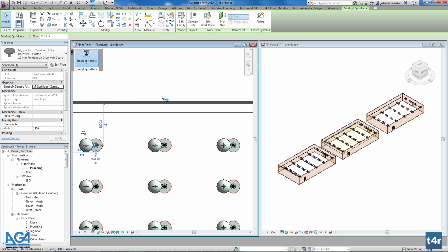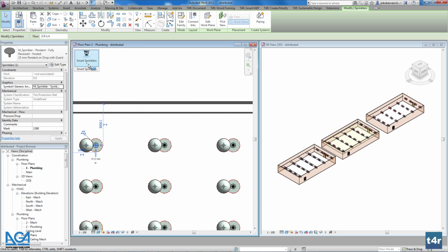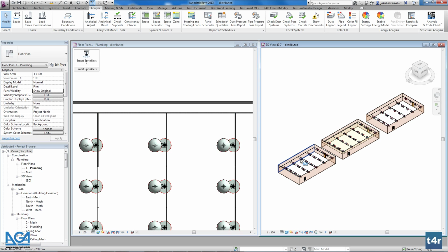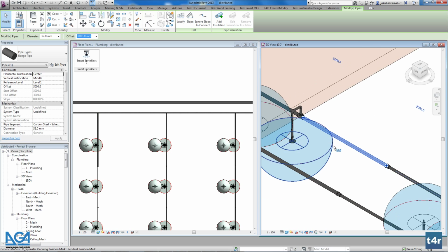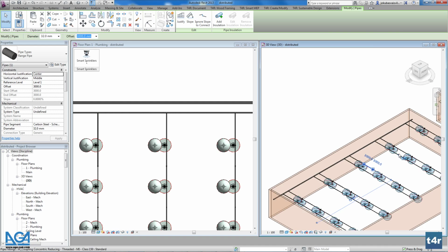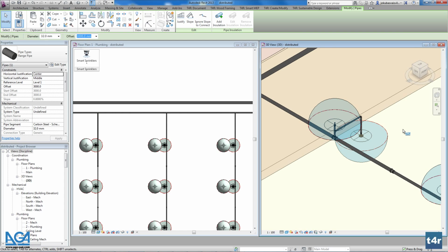There is a possibility to choose different routing preferences. As you saw, I had three rooms with distributed sprinklers, but in each case I used different routing preferences. Here we can define maximum value between two sprinklers, which are connected into one pipe segment. But if the length is too long, the smart sprinkler solution will make a decision to make two pipe segments to feed the sprinkler heads instead. There is a possibility to define where pipes should be connected, either to upright sprinkler or to bended one.